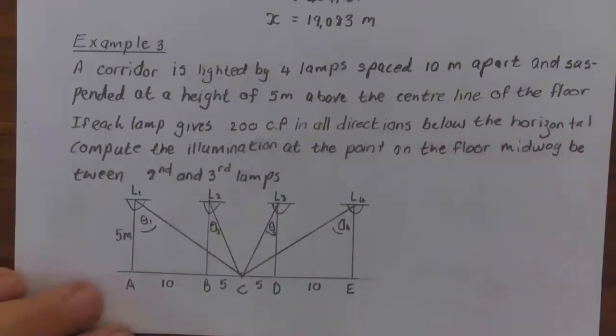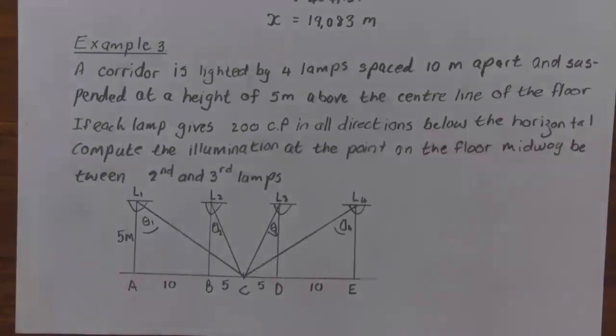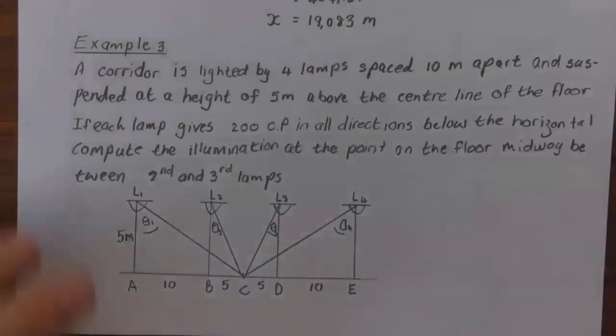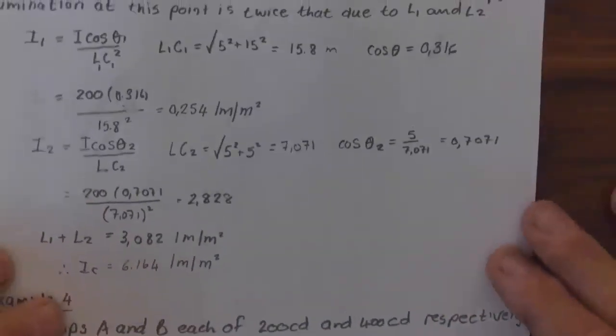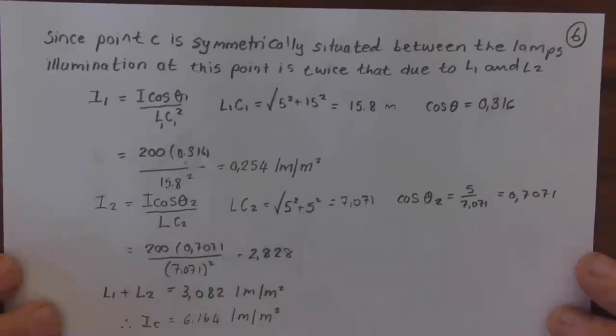Example 3: A corridor is lit by four lamps spaced 10 m apart and suspended 5 m above the centre line of the floor. Each lamp gives 200 candle power in all directions below the horizontal. Compute the illumination at the point on the floor midway between the second and third lamp. Since point C is symmetrically placed, illumination at this point is twice that due to lamps one and two, so I₁ = I·cos(θ₁)/L_C1².